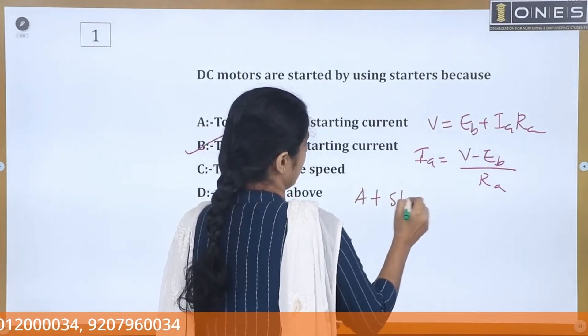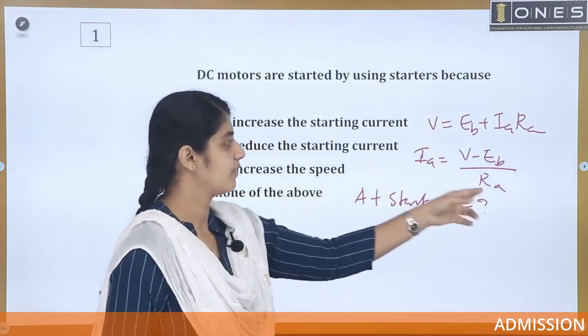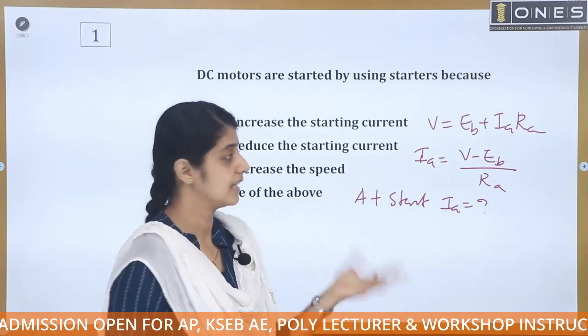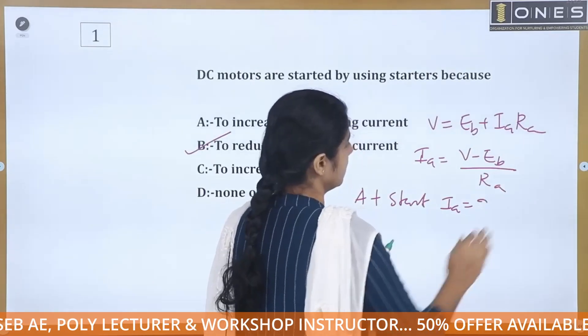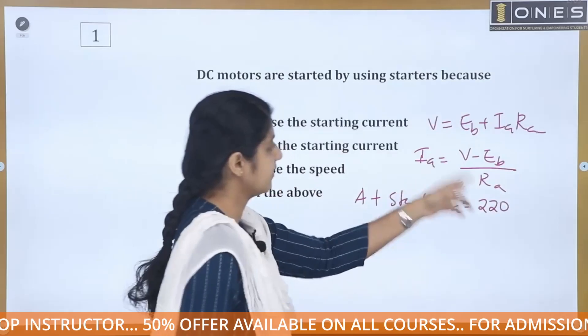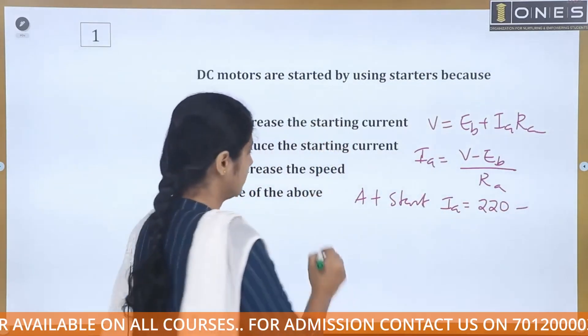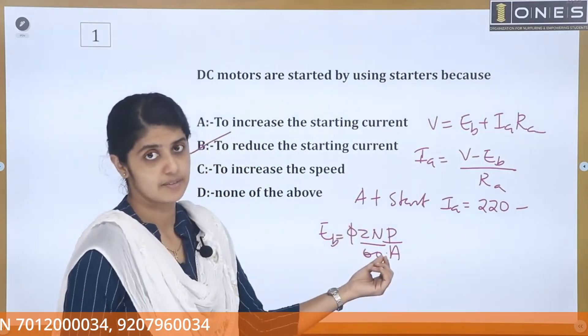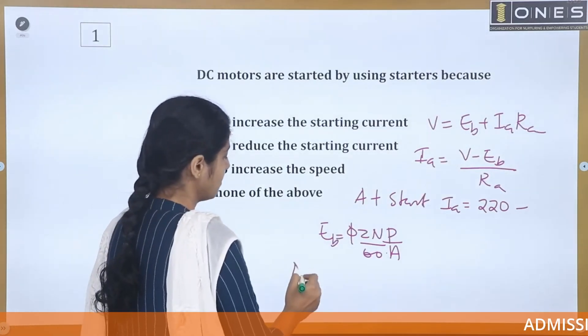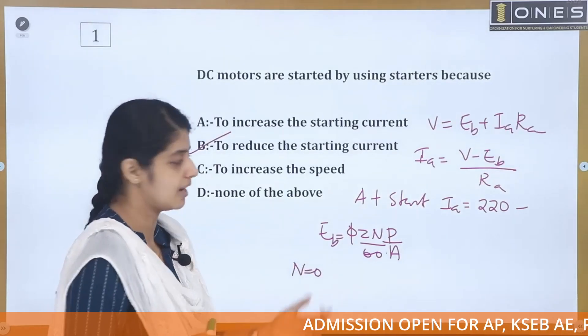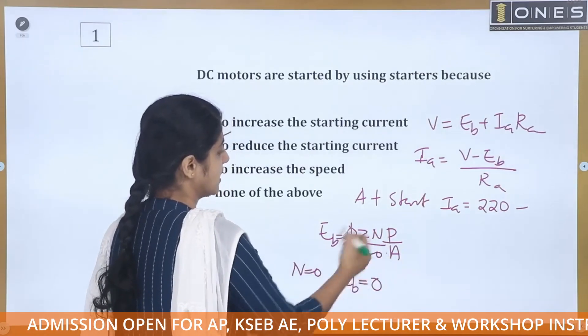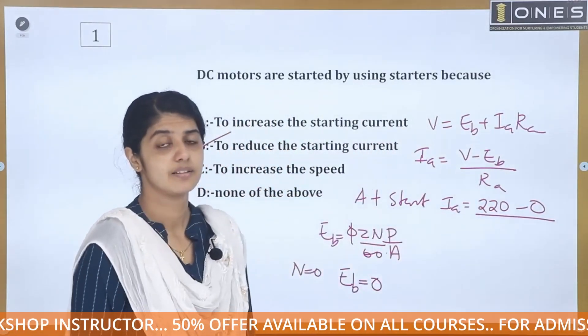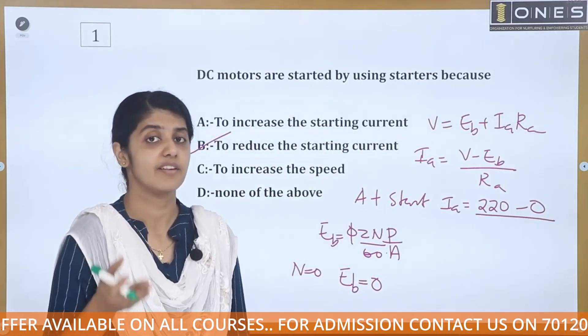At starting, speed N = 0, so the back EMF Eb = 0 (since Eb = φZNP/60A, and N = 0 makes this term zero). Substituting Eb = 0 into the current equation: Ia = V / Ra. With a 220V DC supply and Ra approximately 0.5 to 1 ohm, assuming Ra = 1 ohm, the starting current Ia = 220 / 1 = 220A.